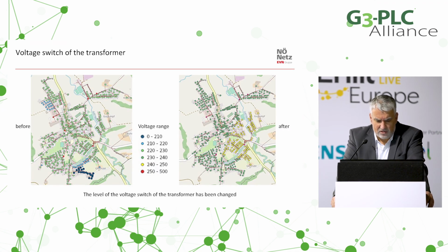Here you see two samples. On the left side the voltage is dark blue, which means it's too low, below 220 volts. We saw that the level of the voltage switch of the transformer has to be changed. On the right side, only by changing the level of the transformer switch, the voltage increased, and in the low voltage grid we always have a very good voltage level.